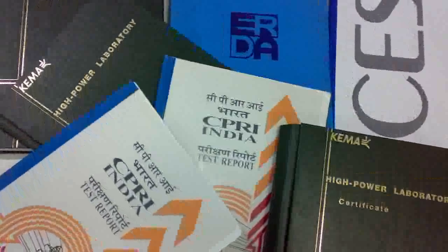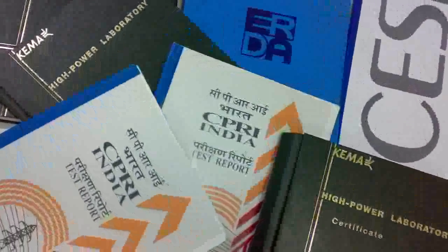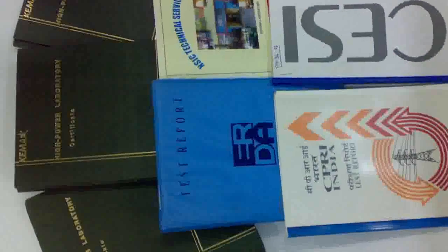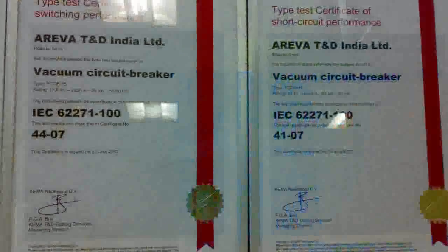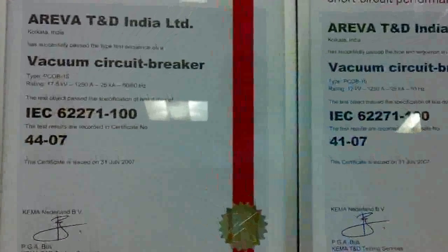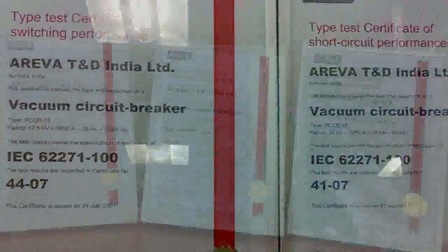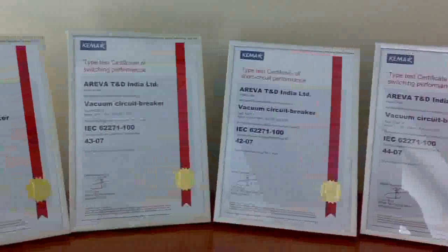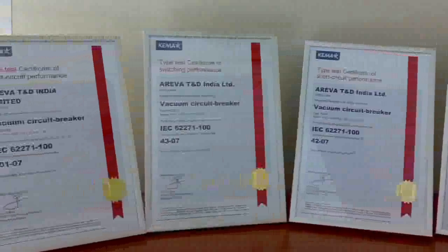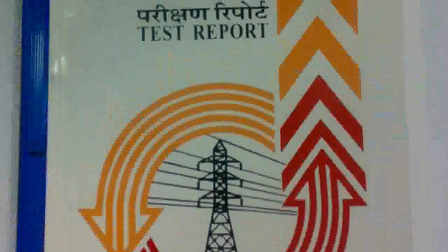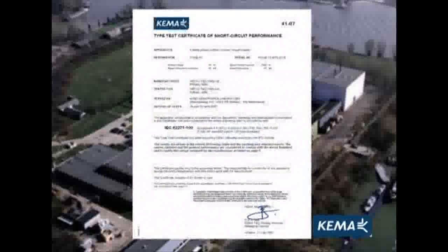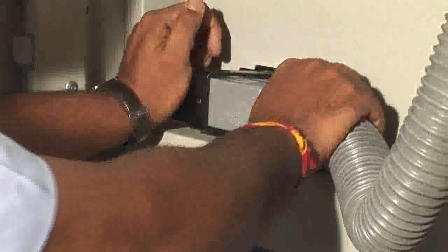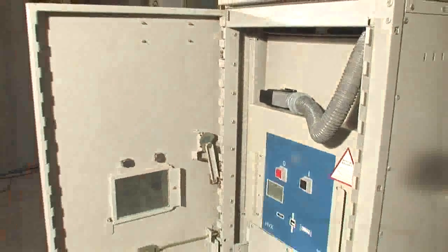How could a customer ascertain if the product in question really meets all the criteria laid down in a standard? The testing laboratories across the world would certify the product if all the tests as specified in the standard have been conducted on a sample which has satisfactorily cleared the test. If not, then a report of performance is given, which may indicate that the test procedure followed has been strictly in accordance with the standard. However, the results may be up to the reader to interpret. The simple choice for a customer would be to ask for the full certification from a reliable laboratory. Strict adherence to the latest standard automatically guarantees the safety of operating personnel.